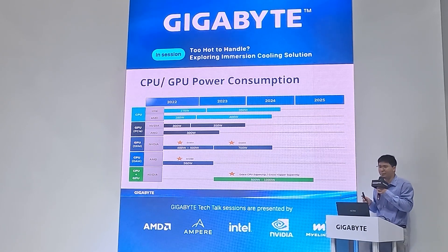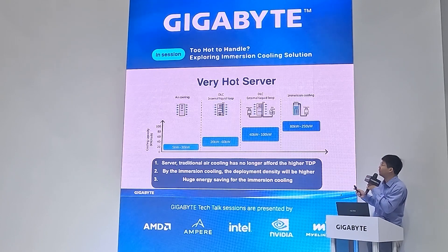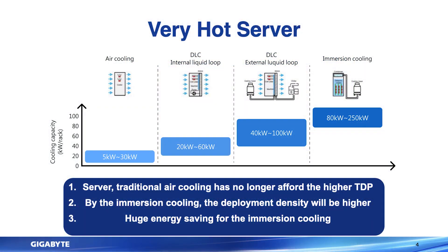With this higher power consumption, we face problems. First, traditional air cooling servers can no longer handle this higher TDP. In this situation, we can use immersion cooling to solve the problem. Second, for cooling capacity, air cooling per rack is normally limited to 30 kilowatts. With immersion cooling, the capacity per tank can easily reach 80 kilowatts — so deployment density is much higher. And most importantly, immersion cooling provides huge energy savings.